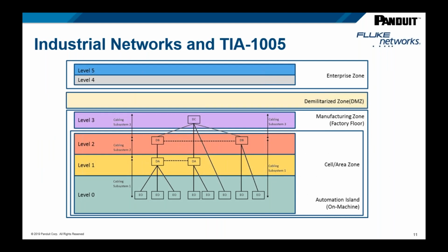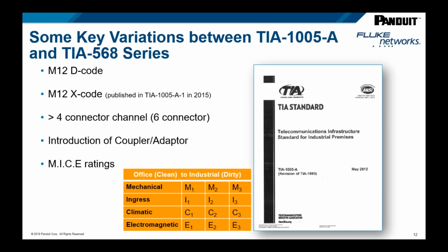I put this overlay of a typical plant floor diagram to give you a feel for where TIA 1005A and the industrial premises typically sits in the industrial network topology. Within the plant floor networks, the structured cabling environment lives alongside the connectivity system for the industrial computing platform at level 3, shown in purple. Intermediate distribution frames, the way we distribute switches out on the plant floor, are at level 2. The more industrial switches at the access layer, deployed in control panels or network zone enclosures, are at level 2, 1, or 0. That's the basis for how this correlates with the industrial network.